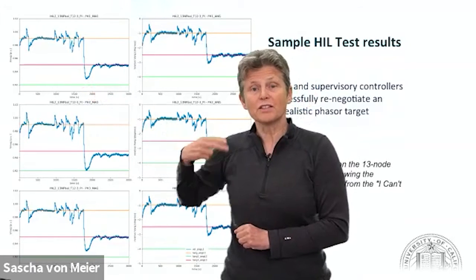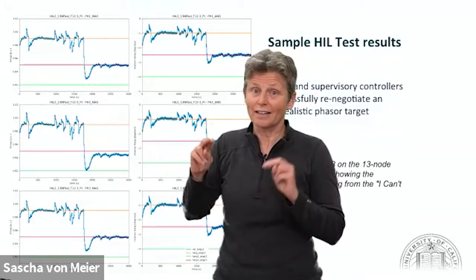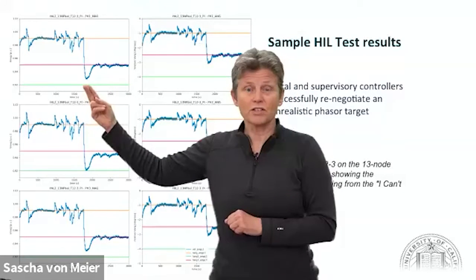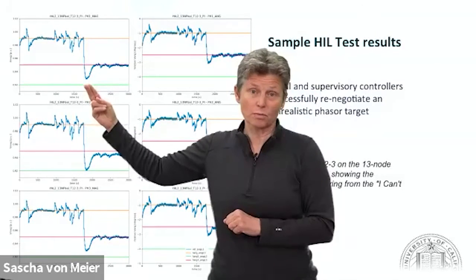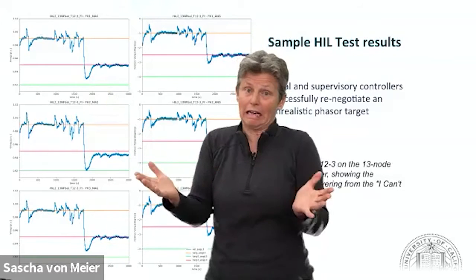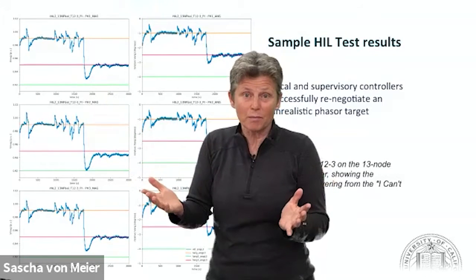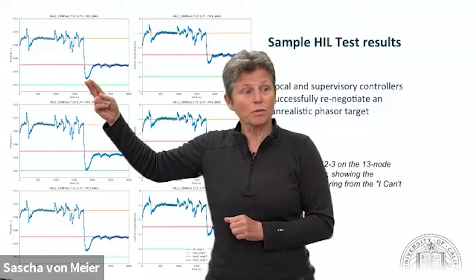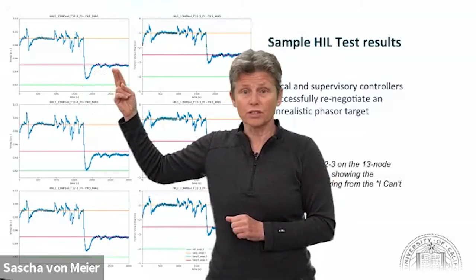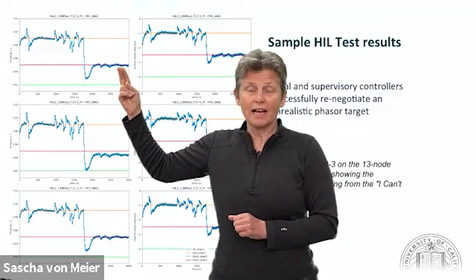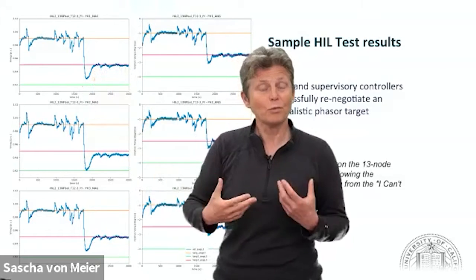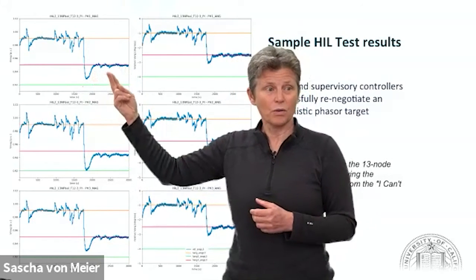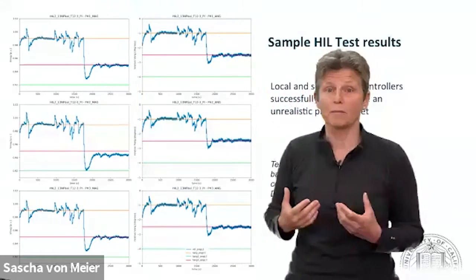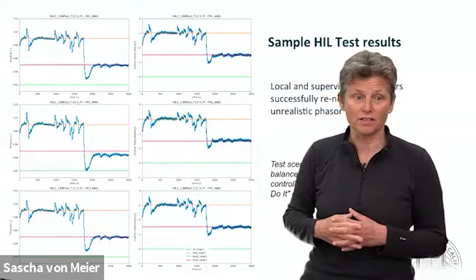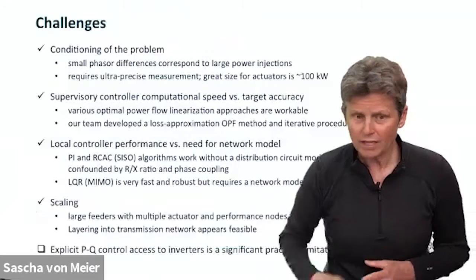So we implemented this feedback, which we called the 'I can't do it,' where the local resource communicates to the supervisory controller saying, hey, your target, I can't do it, give me something more reasonable. The supervisory controller then reissues this red target, and the actuator says, okay, we can get there. So that was an important demonstration of the robustness of the system.